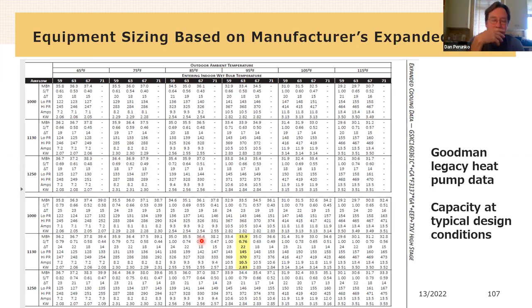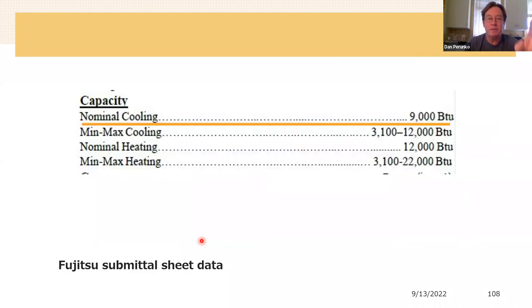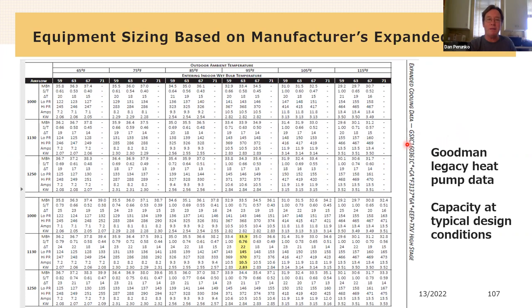And I don't, pardon me, have time to spend a lot of time on this, but the thing we need to avoid is this. This is called the submittal sheet. And so it's the thing that you would turn into an architect saying, this is what I'm going to install. And it gives you, you know, this is a 9,000 BTU unit, and it has between 3,000 and 12,000 BTUs of cooling capacity. And you have no idea under what conditions that occurs. You have to go into what's called expanded data, which is this thing. And in this particular sheet, you're seeing airflows over here and outside conditions over here and capacities in here.